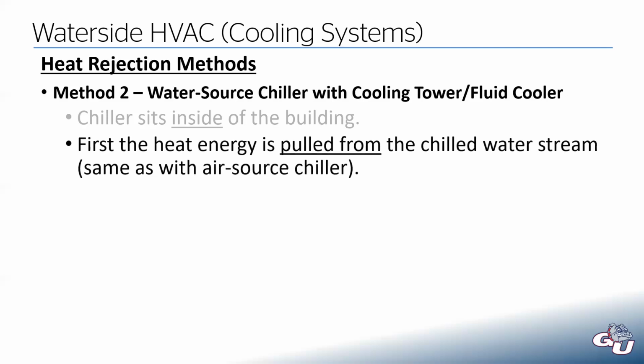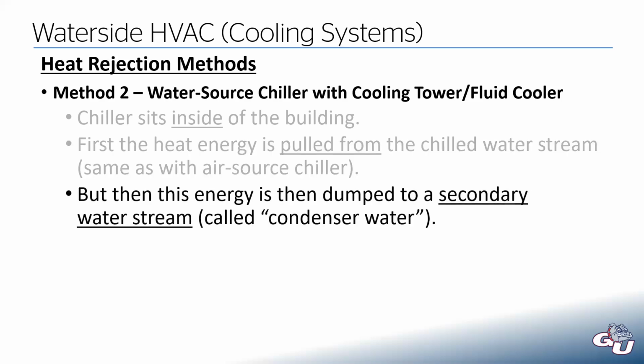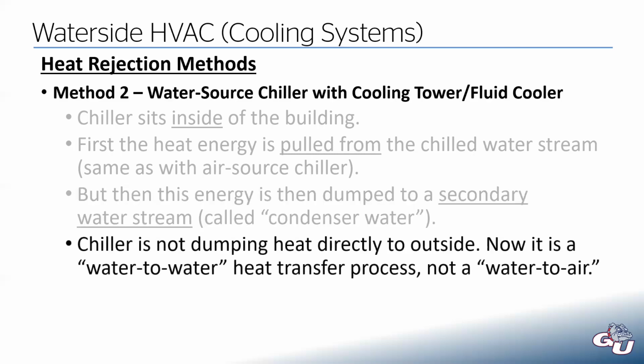First, our heat energy is going to be pulled out of our chilled water stream. That part's not any different. We're still coming back with warmish chilled water, and then we're going to be pulling that energy from our chilled water stream. But the difference here is we're then going to dump that into a secondary water stream, which is called condenser water. So on one side of our chiller, we have chilled water. On the other side of our chiller, we have condenser water. So now the chiller, which remember is inside the building, is not dumping heat directly to the outside. Now we have a water to water heat transfer process. It's not a water to air heat transfer process.